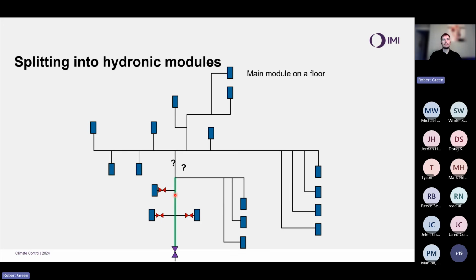A little bit more complicated at this intersection. Is the main flow going to the right or is it going straight up? Now here we need to know something about the flow in these units. For the sake of argument, we're going to say all of these units are identical to make our life 10 times easier, and I don't need to know the flow. But if we were working with drawings, on the drawing itself, it should be written what the flow is. So the main flow is still going to be carrying on up the way. So we place a manual balancing valve on the right hand side and we carry on to the next intersection.